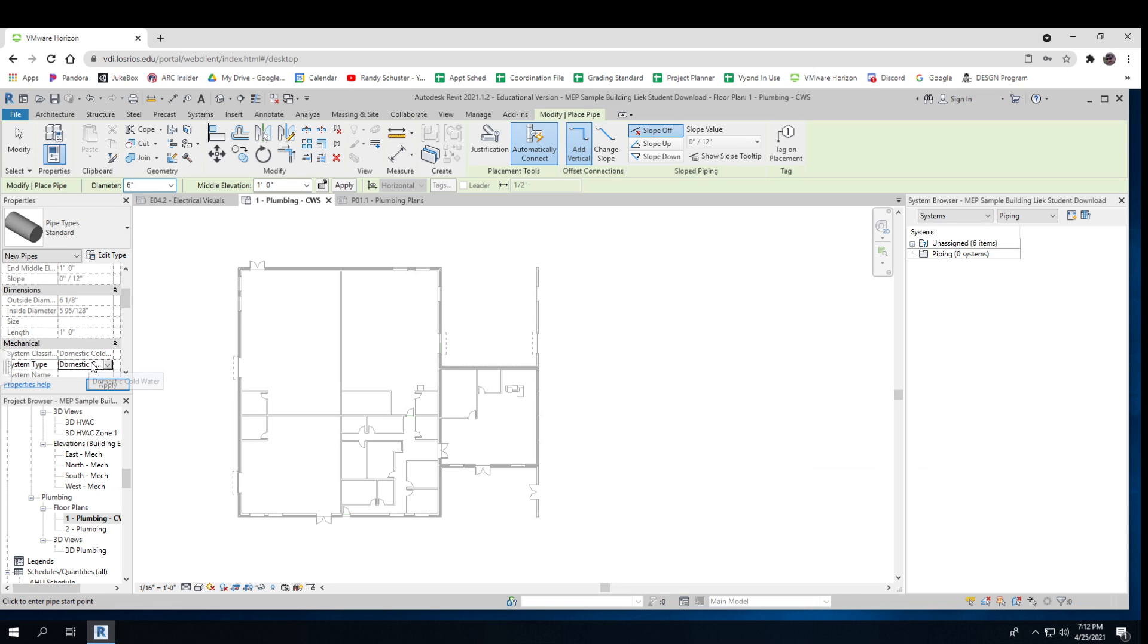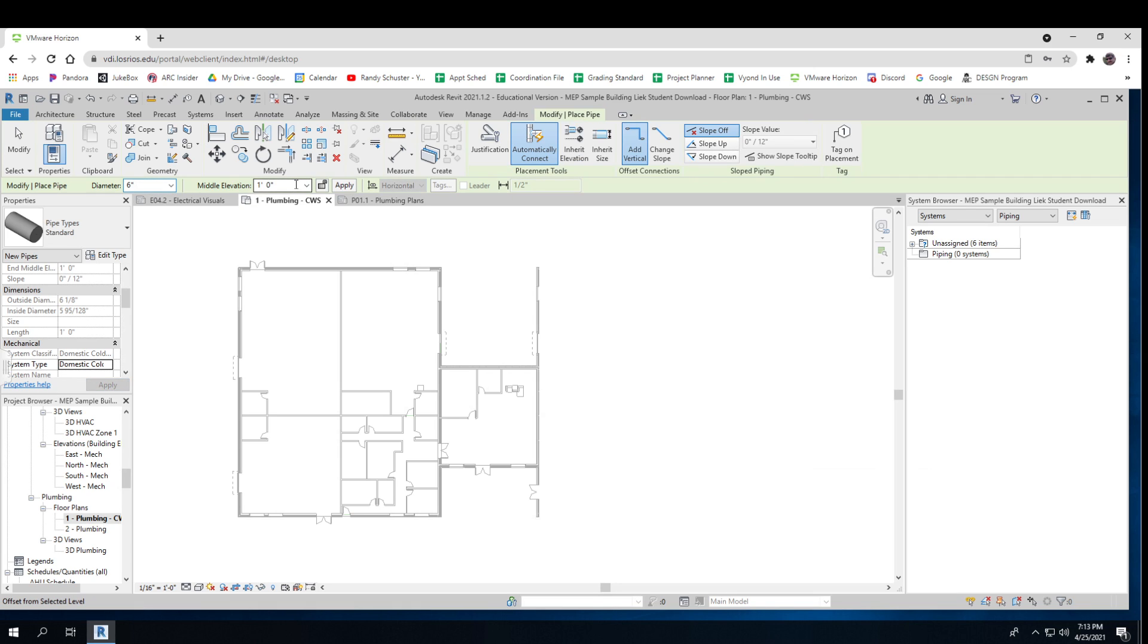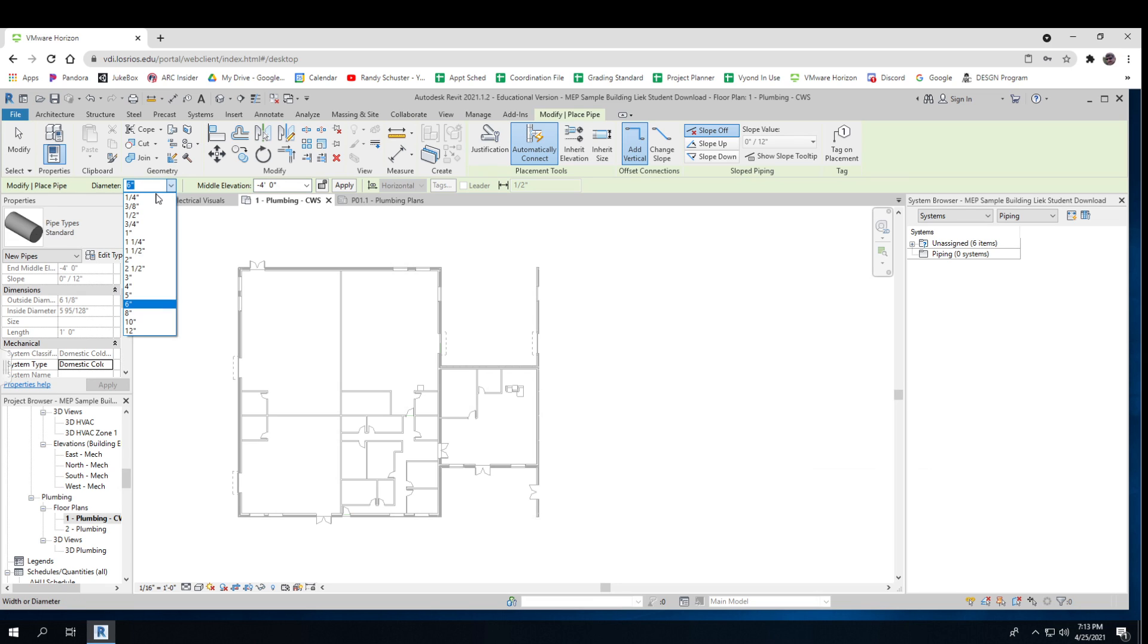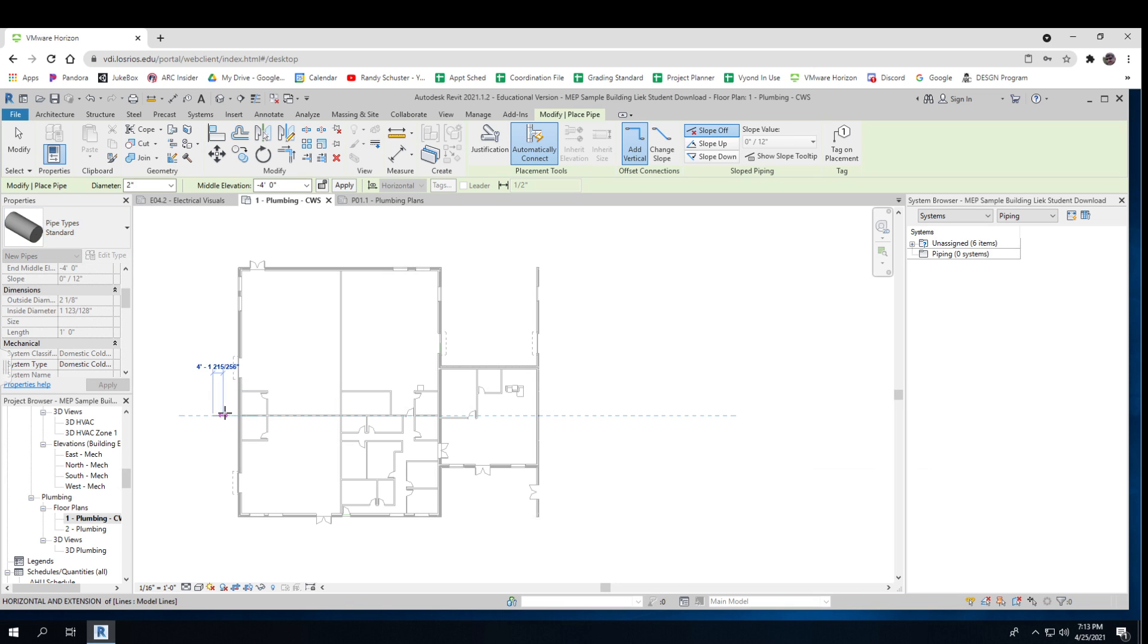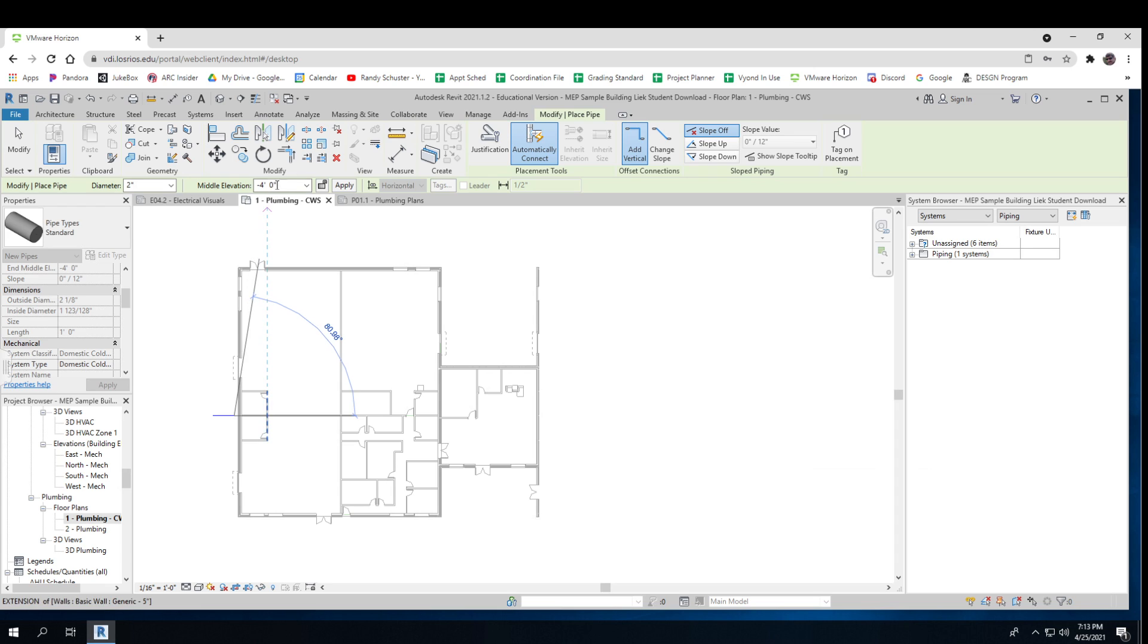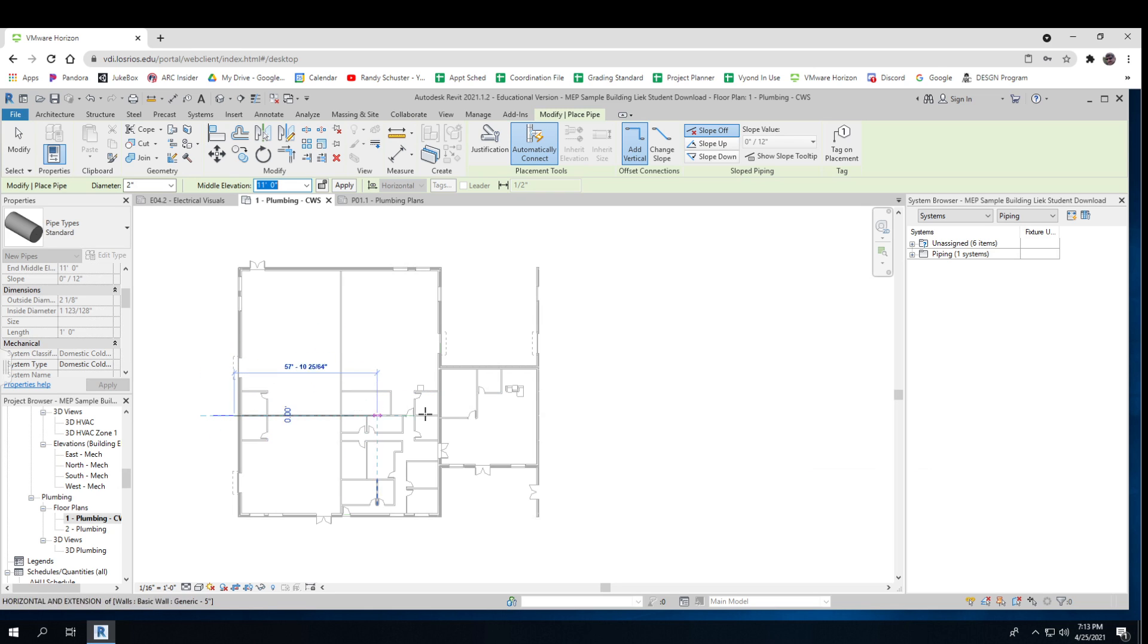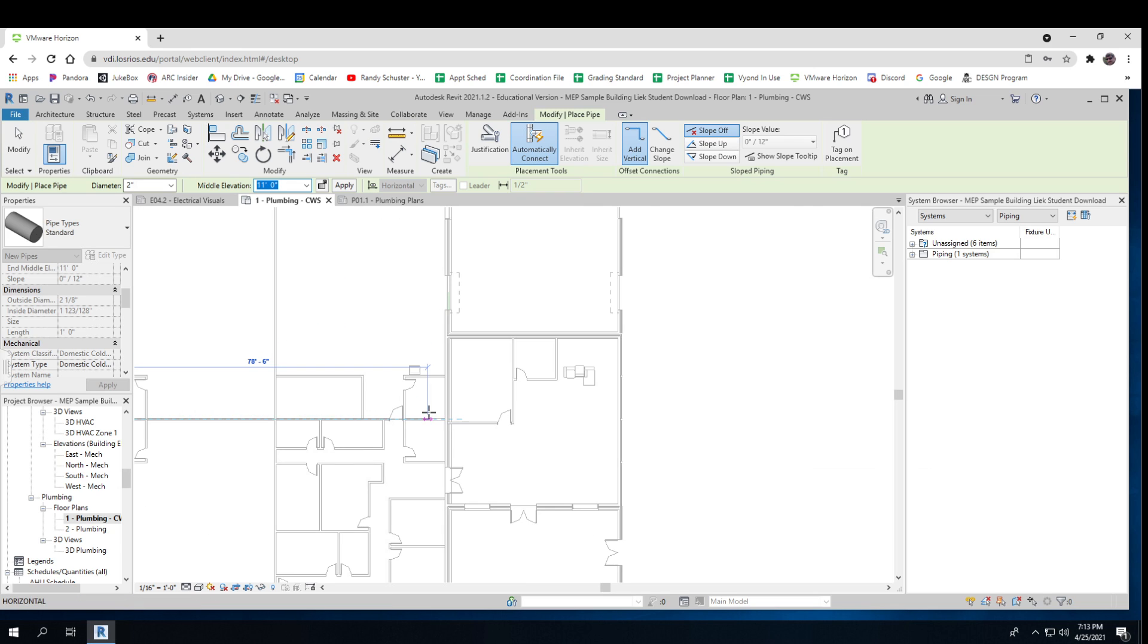Now I can put in my middle elevation, which I said was going to be minus four feet, and the size was going to be two inch. And I'm just going to use just a standard pipe, that'll be fine. So I'm going to run it in until it's somewhere near the wall. And then I'm going to change my middle elevation to 11 feet and I'm just going to continue it right over to here. Enter.